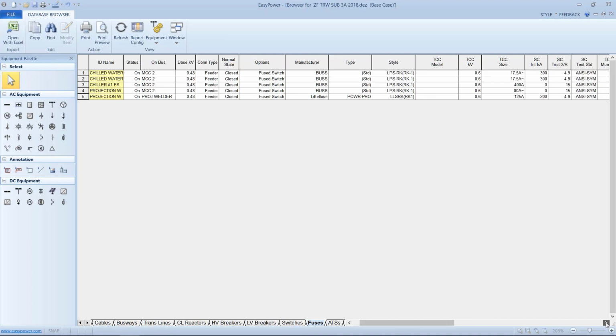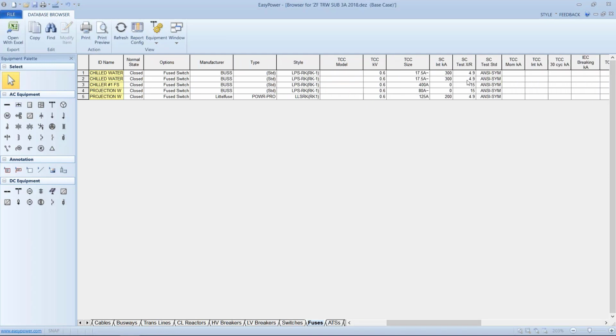Another flag, or another clue to the problem, is here we show a test environment for short circuit X over R value of 4.9, and for these other 2 it's 15, and yet they're all hanging on the same 480 volt bus. EasyPower automatically compensates the X over R that the manufacturer uses in the plant to test the component for our equipment duty ratio. And the fact that we don't have numbers in here that reflect what the manufacturer represented means the tool's not doing its job, or at least it's not providing the assistance that it can provide.